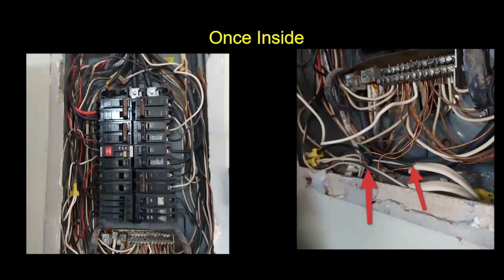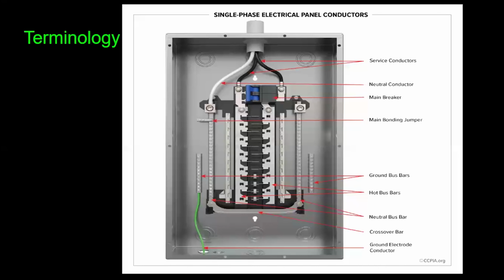The other thing I noticed, going back on the circuit breakers, is that the lowest breaker there was a 20 amp circuit breaker. Every single one of those wires coming off it were 12 gauge wires. Then I followed the 12 gauge wire and it goes to a 14 gauge wire right inside the electrical panel box. That's a safety hazard because the 14 gauge wire really shouldn't be taking on 20 amps. So keep an eye on that kind of stuff when you're doing the electrical panel.